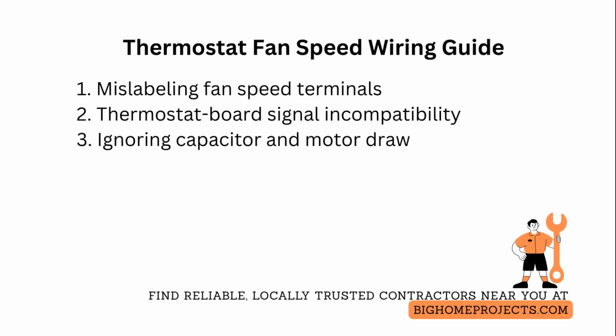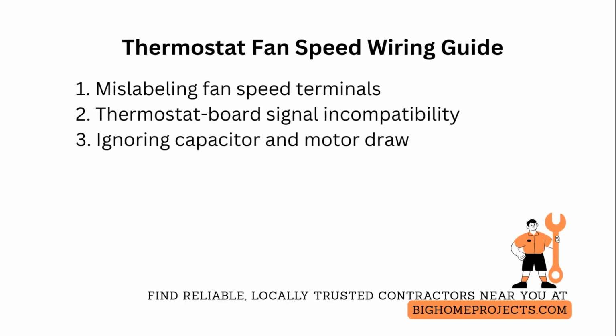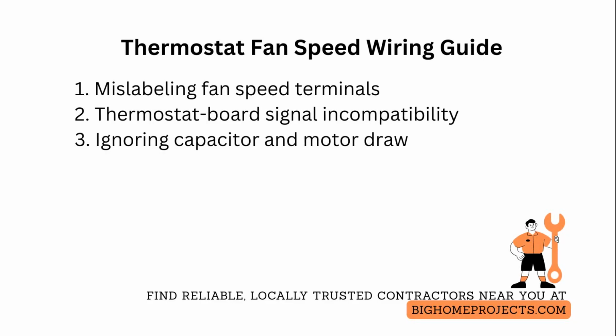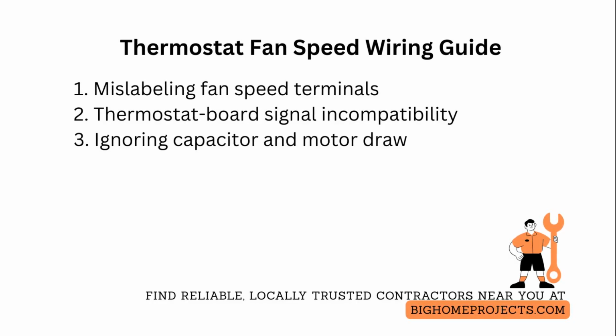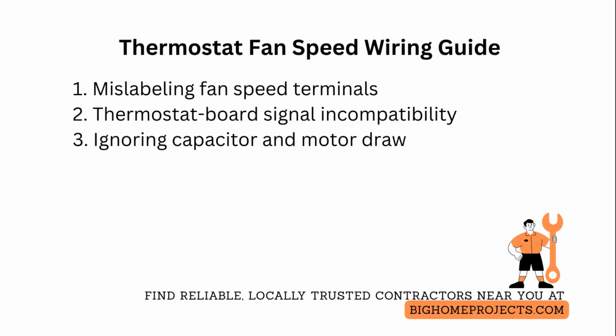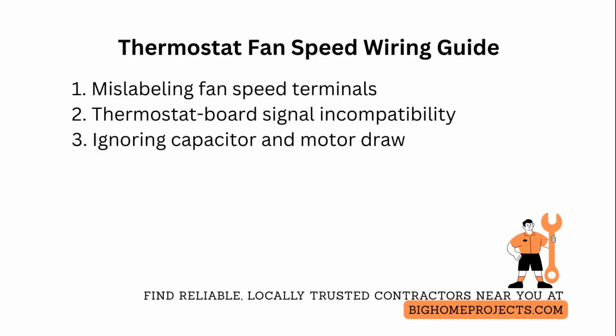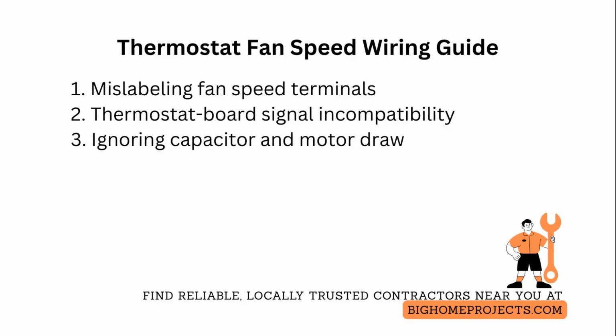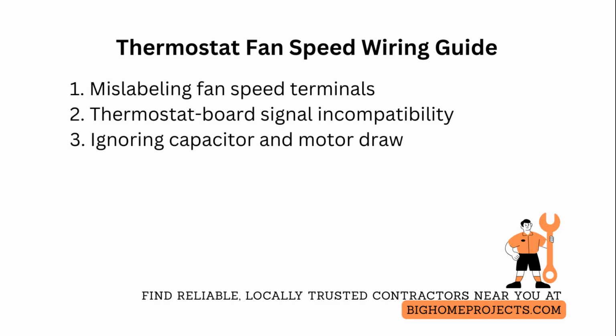One of the common thermostat wiring mistakes is mislabeling or misconnecting fan speed terminals, causing improper blower speed during heating and cooling. Fix this by tracing and labeling each motor lead, consulting the control board schematic, and using temporary jumpers to verify speeds. One of the frequent issues is using a thermostat that outputs a variable signal incompatible with the furnace control board, which causes erratic fan behavior.